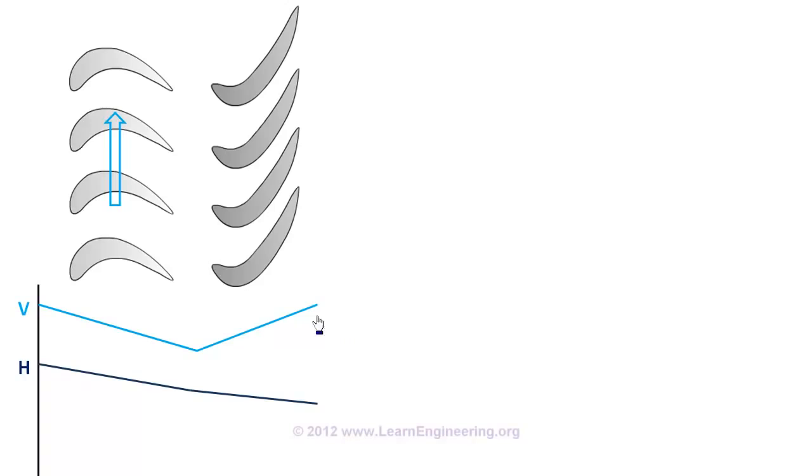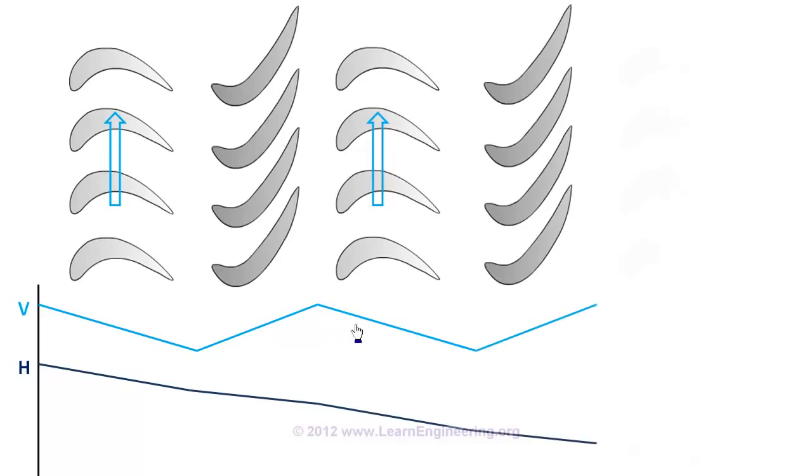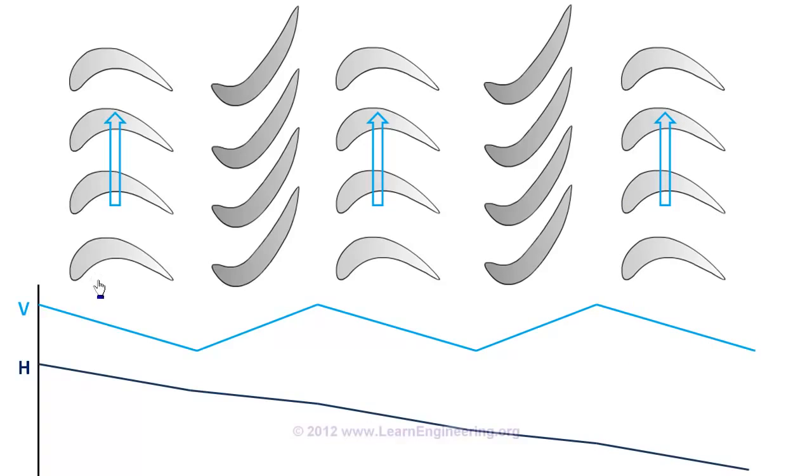Now we have increased velocity of fluid, so we can put next set of rotor. Again stator. And again rotor. So in a steam turbine there will be alternating sets of such rotors and stators. Rotors which are moving attached to the hub. Stators which are stationary, attached to the casing of turbine.